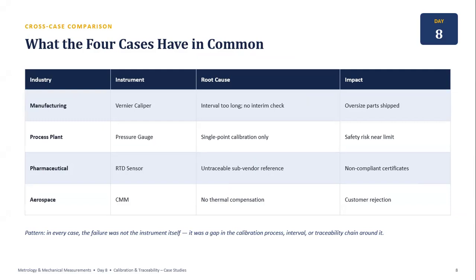Now let us have a comparison between all the four case studies in common. Across manufacturing, process industries, pharmaceuticals, and aerospace, a common pattern emerges. The problem was not necessarily a defective instrument. Instead, the failure resulted from gaps in the calibration interval, calibration method, traceability chain, environmental control, or verification process. There are several common pitfalls that organizations should avoid. First, do not depend blindly on fixed calendar-based calibration intervals. Second, never rely on single-point verification when the instrument operates across a wider measurement range.